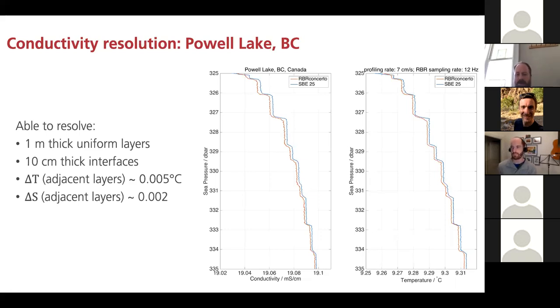You know, we're in 19 millisiemens per centimeter here. Certainly, I think we're outside of PSS 78 completely. But you can see we've got a Seabird 25 strapped there. We've got the Concerto. Concerto is about a quarter of the price of a Seabird 25. And both of them are able to see these conditions. We're running only at 12 hertz, and they are deploying the winch at about 7 centimeters per second. It's a bit slower than, it's on the same order as an Argo float. And so we've got 2 milli-PSU salinity in effective salinity, and 5 millidegrees in adjacent layers. So a nice example of the kind of resolution that you can get with an RBR with no special prep, no data treatment, there's no averaging or anything going on in this data. It's 12 hertz data right out of the instrument.